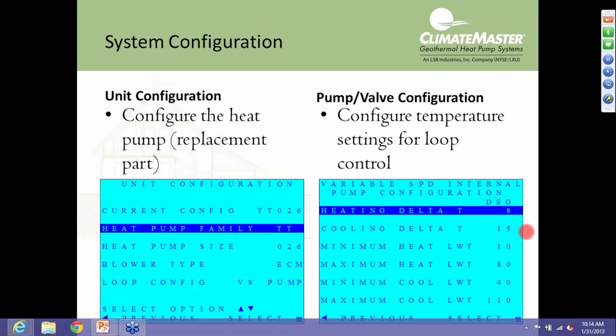Also under loop configuration, if your unit has a modulating valve, we have the modulating valve option. And then there is an option there for none. If you choose none, your pump or your valve will not work. So again, that's the only option in these heat pumps, so you're going to have to choose one or the other if you're configuring this unit. Again, the default, if you've got a variable speed pump, will be variable speed pump in single. So if you're doing a parallel pumping option, meaning you've got that unit with another unit on a common loop, you must choose variable speed pump in parallel.